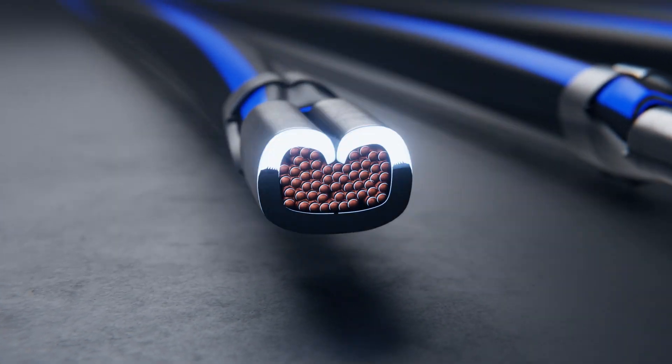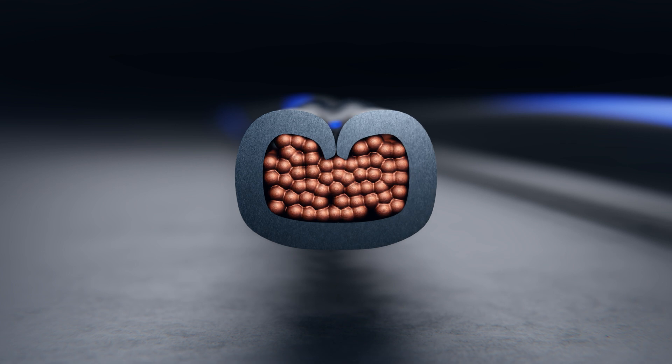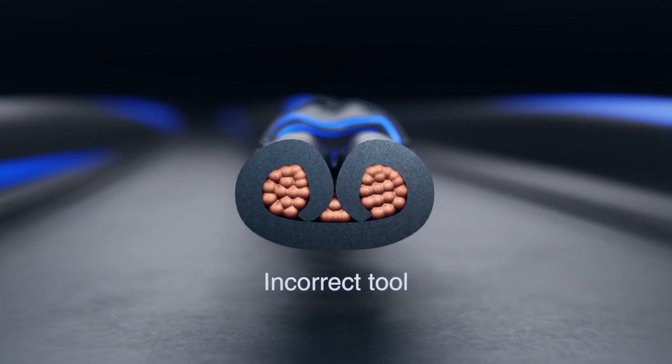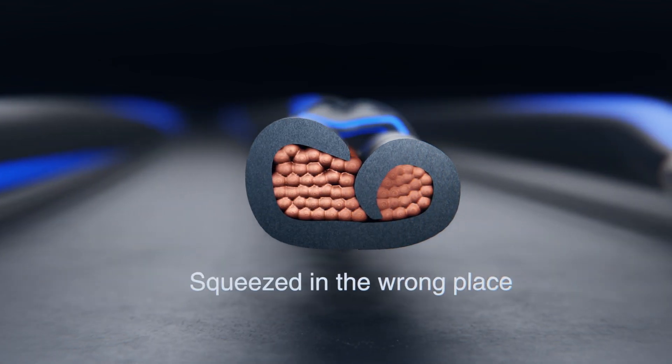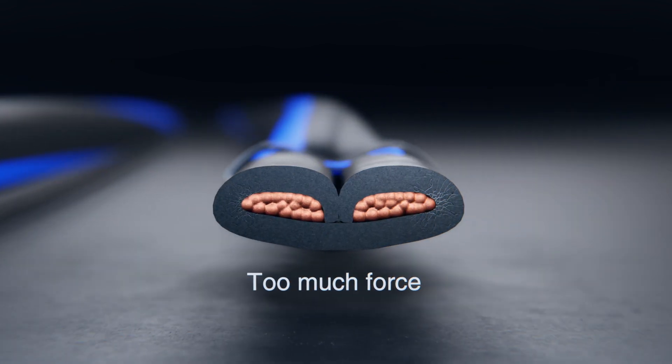Let's take a close-up look at some bad crimping pictures. What are common failures caused by using the wrong tool? Crimps that are too loose. Mismatch between terminal and tool causing incorrect shape. Terminals squeezed in the wrong place. Too much force resulted in damage to wire and terminal.